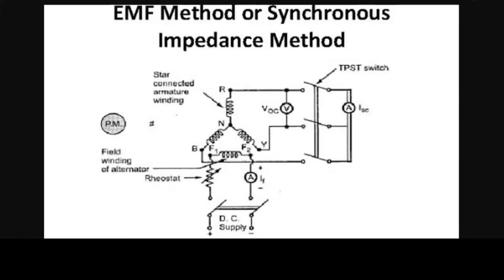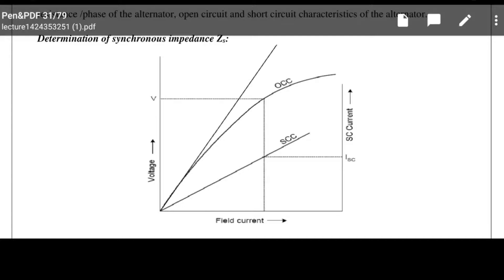For the OCC test, by gradually increasing the field current at constant synchronous speed, the open circuit voltage generated is noted down. After that, for the same field excitation and constant speed, the TPST switch is closed. This causes short circuit current to flow through the ammeter. This short circuit current is set to the rated current of the alternator. The OCC and SCC tests are carried out this way, and curves are drawn — IF versus VOC for the OCC and ISC versus field current for the SCC.